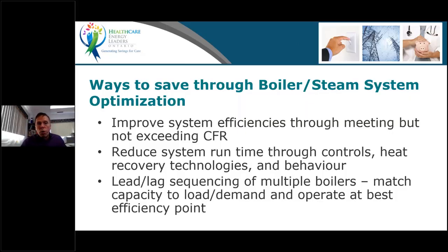How you sequence your boilers will also have an impact. And actually I was going to say mostly for hot water, but that's true also for all the systems. So are you using lead lag when you have multiple boilers? It will depend on the load, how your efficiency varies with load. So if you've got condensing boilers, for example, you very often should not use lead lag.